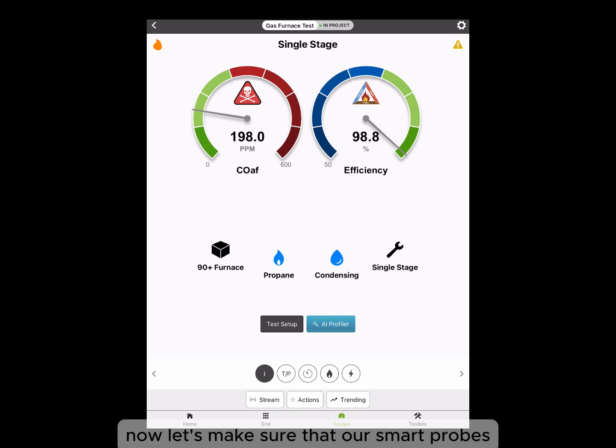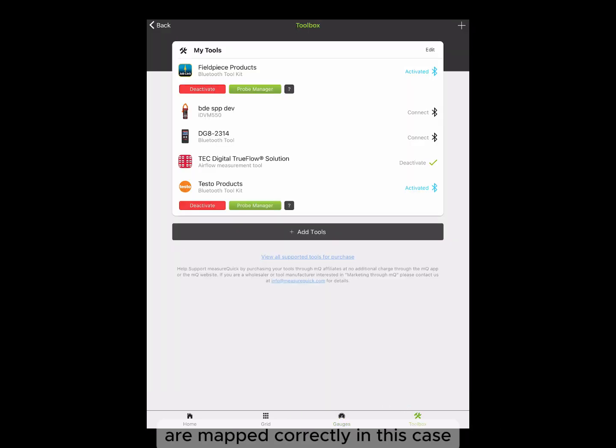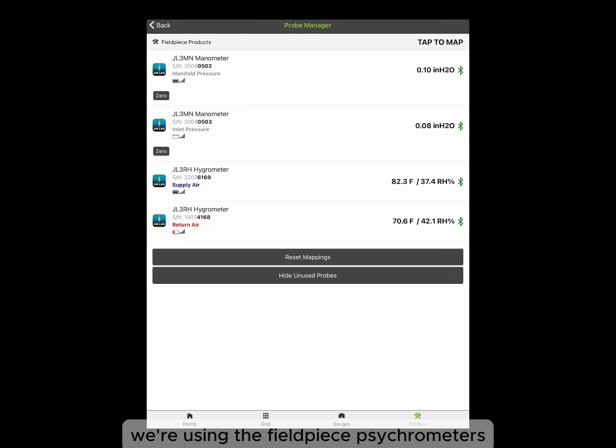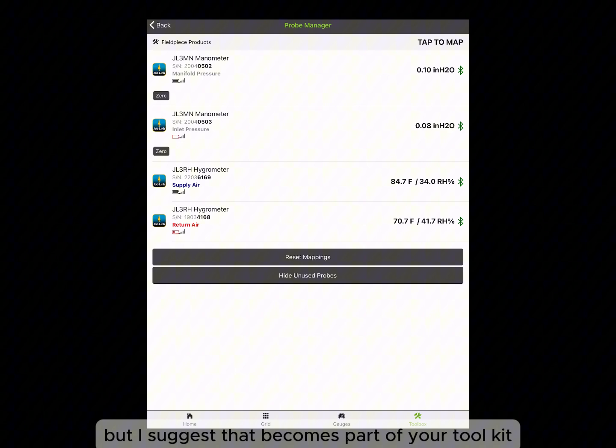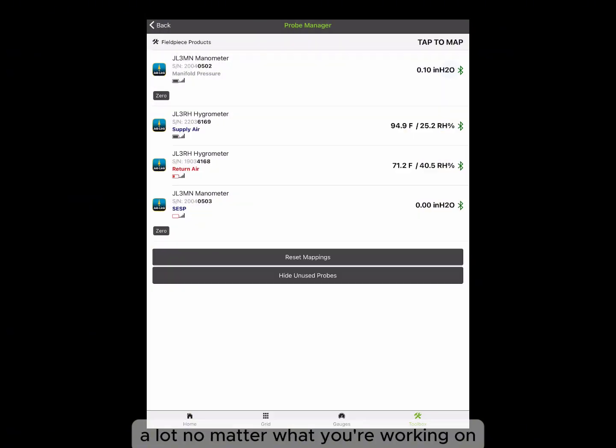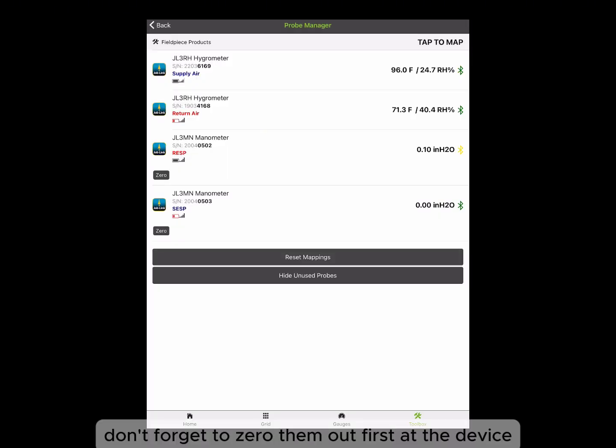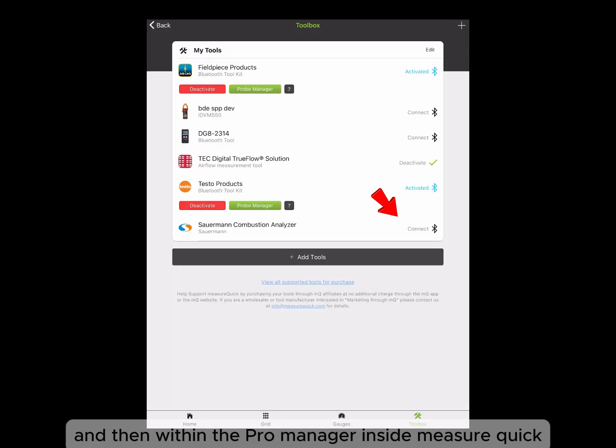Now let's make sure that our smart probes are mapped correctly. In this case, we're using the Fieldpiece psychrometers for return and supply, and I also have the Fieldpiece job link manometers. These are Bluetooth manometers that do talk to measureQuick. You don't have to have them, but I suggest that becomes part of your toolkit because you're going to be reading static pressure a lot no matter what you're working on. And we're going to map them to static pressure in this case. And as always, don't forget to zero them out, first at the device and then within the probe manager inside measureQuick.